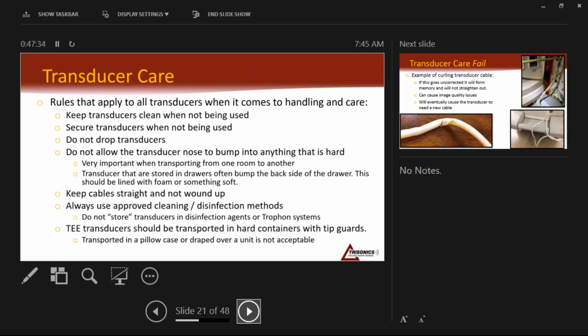Don't drop transducers. We like to call this, in technical terms, vertical deceleration trauma. But a dropping of a transducer used to be, we would say, if you drop a transducer from a foot or two, it'll probably survive the damage 15 years ago. But the way transducers are today, if you drop a transducer at 6 inches, it probably will not survive the damage. And some transducers, that's down to about 2 inches now. So they are just far more fragile today than they ever have been.